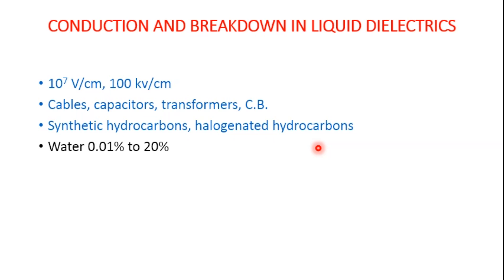Petroleum oils are the most commonly used liquid dielectric media. Synthetic hydrocarbons and halogenated hydrocarbons are also used for certain applications. Liquid dielectrics are normally a mixture of hydrocarbons and are weakly polarized. When used for electrical isolation they should be free from moisture content, products of oxidation, and other contamination. If there is a presence of only 0.01% water content in dry transformer oil, the dielectric strength will reduce by 20%.